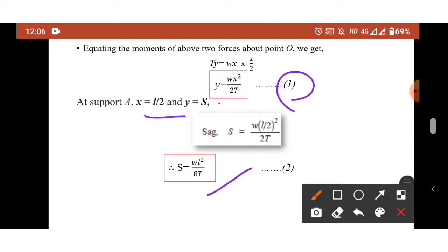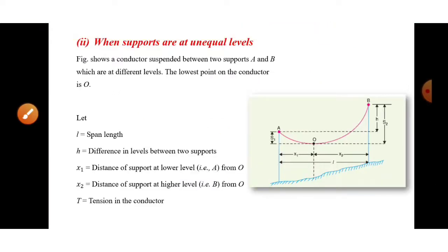So the general equation for sag when supports are at equal levels is S = WL²/8T. Now let us consider the second case — when supports are at unequal levels. In hilly areas, supports will be at two different levels, so we calculate sag for such cases.